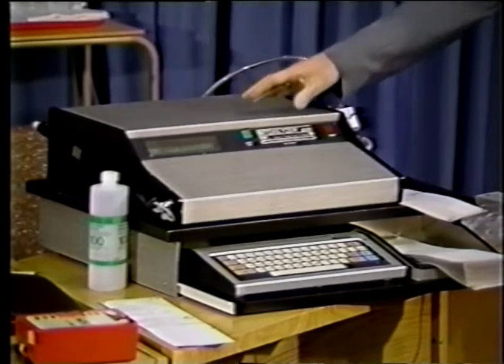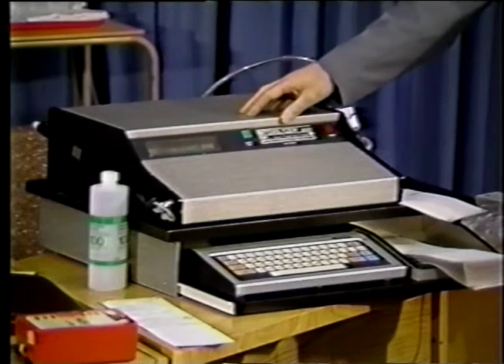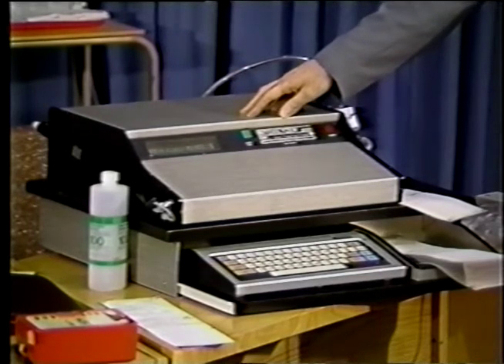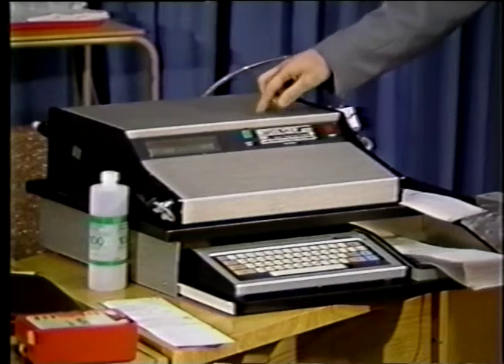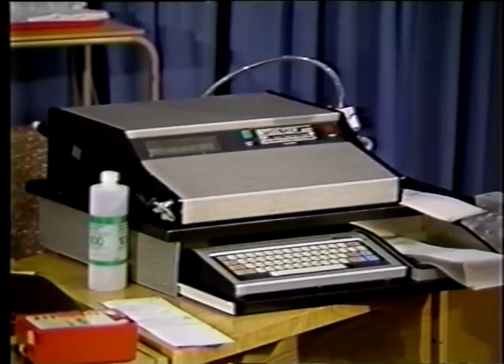Now, it is a new type of device with new detection. However, the same procedures still apply under the Criminal Code and also under our procedures. Number 1, you have to do 2 subject tests and they have to be at least 15 minutes apart. That still applies even though we're using a new device. Number 2, it has to be checked using an alcohol standard, and this will also be checked using an alcohol standard. Number 3, for our quality control, the 2 results must be within 20 milligrams of each other, the truncated results. So although it's a new device for detection, it's a nicer way of detecting alcohol. The same standards and criteria will apply.